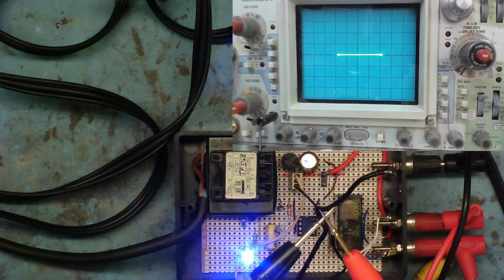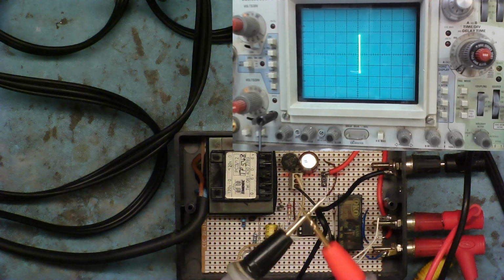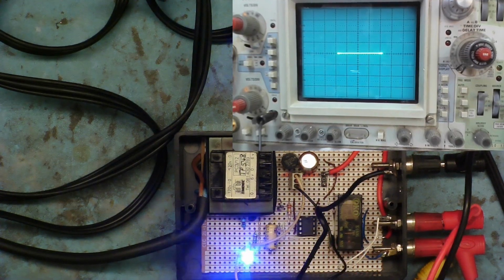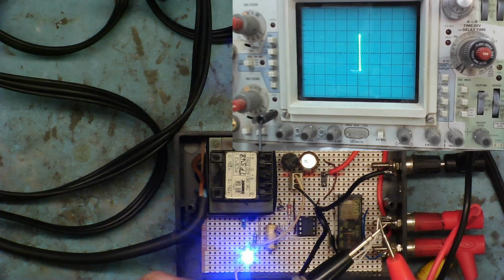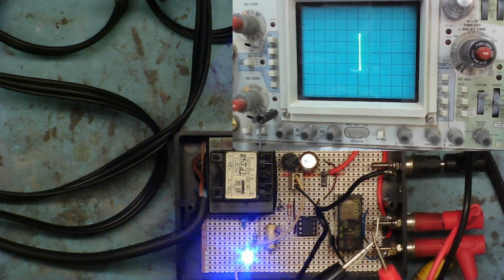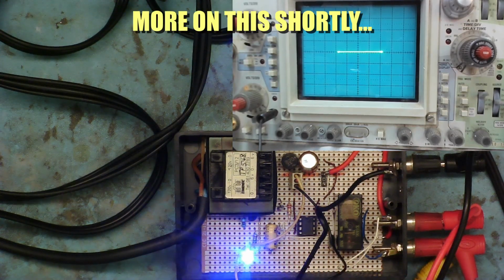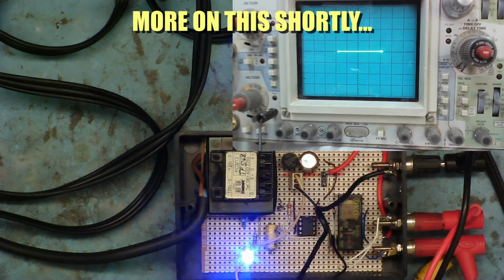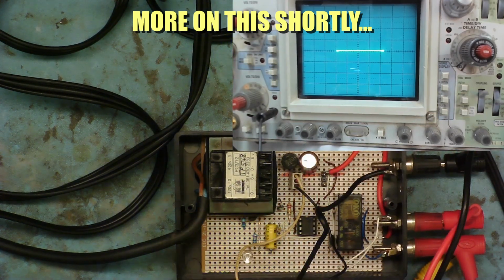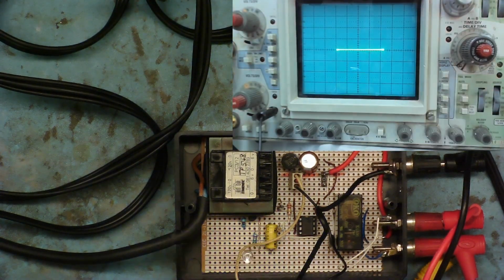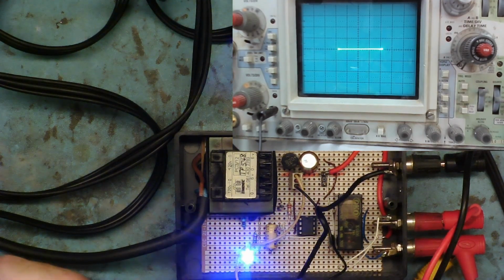And you can see it's basically switching as you'd expect it. But it does slow down a little bit. If we connect the other one, it actually speeds up a little bit. It seems to me that what's happening is that the fact the relay is drawing current from the transformer is altering the voltage slightly. So why I think this is actually kind of like moving in and out a little bit. Just try a diode.